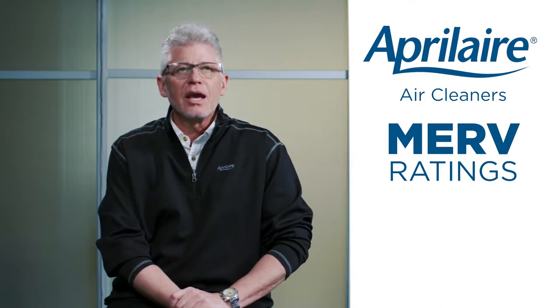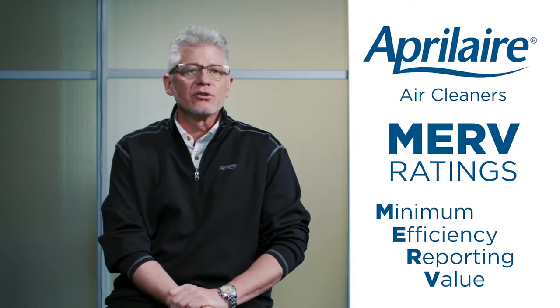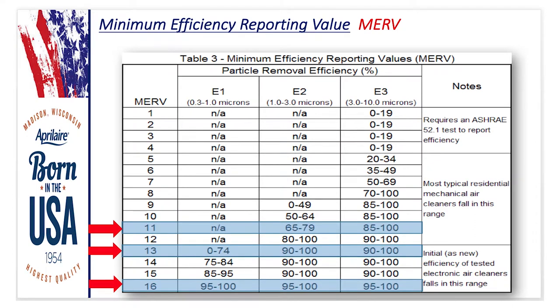A lot of you have heard the word MERV. MERV stands for Minimum Efficiency Reporting Value. It's an industry standard that rates the particulate capacity and size that an air filter media or air cleaner can capture. There are three important areas: MERV 11, MERV 13, and MERV 16. MERV 11 is the first measurement that rates anything catching particulate in the E2 bin — things that are one to three microns.